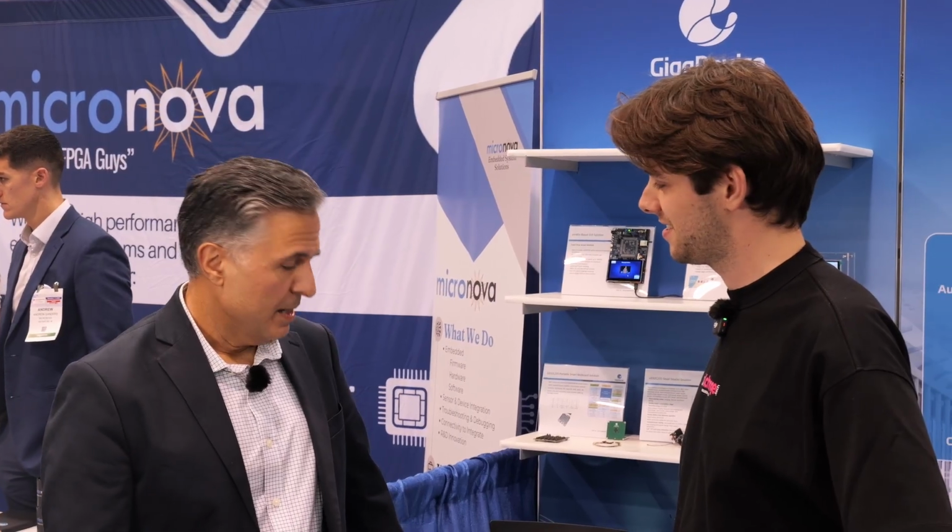Blisteringly fast. As you can see, the efficiency for this PSU is 97.8%. That's good. For a 12 kilowatt PSU in an AI data center, where power requirements are obviously a big requirement, because you don't want to create a lot of nuclear plants to be able to support data centers. Every single 0.1% efficiency gain means real dollars to the end users of the data center.